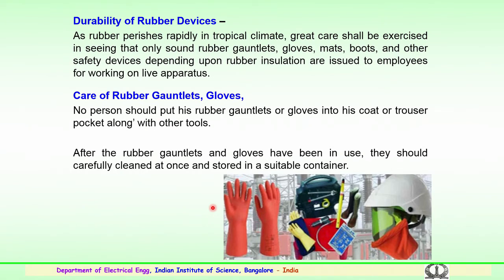As mentioned earlier, the devices have to be verified for durability, proper care has to be taken, and proper storage has to be done. For example, in the case of rubber devices, we know that rubber perishes rapidly, particularly in a tropical climate. So, utmost care has to be exercised in seeing that these rubber gloves or gauntlets, mats, shoes and other safety devices are properly checked for insulation, as they are used by employees particularly for working on live line apparatus, which is very important. Care of the rubber gloves has to be taken so that no person puts his gloves into his coat or trouser pocket along with the tools. They have to be maintained separately.